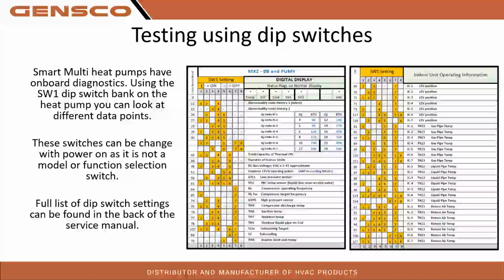Yes, that is correct. Stan has a question. Can the codes be cleared from the outdoor unit with dip switches? Yes, they can. If you guys have an error code, SW2 switch 2 on your heat pump will clear that error code.